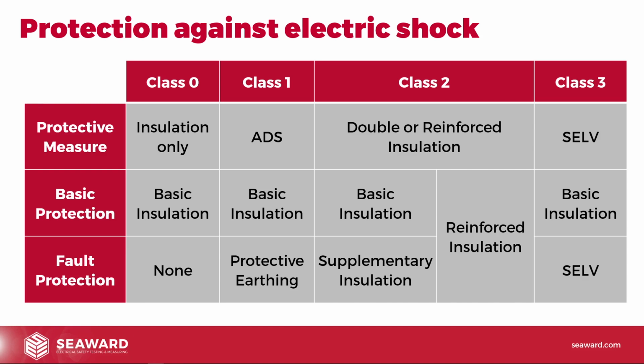So if we start off with Class 0, as we said, Class 0 is quite old-fashioned now and something we would probably fail on site. So in this case, Class 0, the protective measure, there's only insulation. That's all we've got. And we've got basic protection provided by basic insulation. So you remember those Christmas tree lights, we've got the basic insulation, that transparent green insulation around the wire. And fault protection, nothing. So if that fails, we've got no fault protection. So in that case, that's why that's seen as dangerous nowadays. It's not seen as being good enough. We always need to have a combination of basic protection and fault protection.